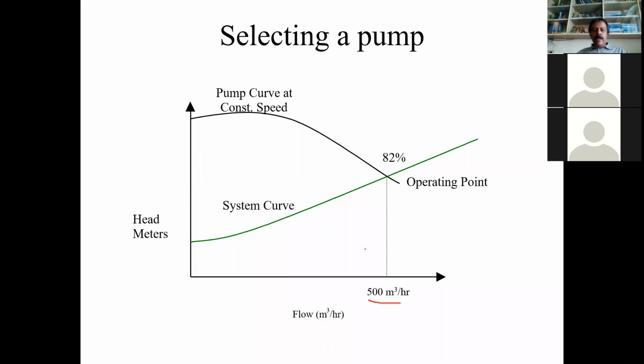Now, as you start operating the pump, you find that the requirement is only 300. The pump is now delivering 500. The requirement is only 300. So how to make this 500 meter cube per hour pump operate at 300? Which means we have to throttle the pump. So the simplest thing is to close the valve a little bit. So when you close the valve, what happens here? You're going to take it like this. Increase the head. Closing the valve means increasing the head. So now we are closing the valve.